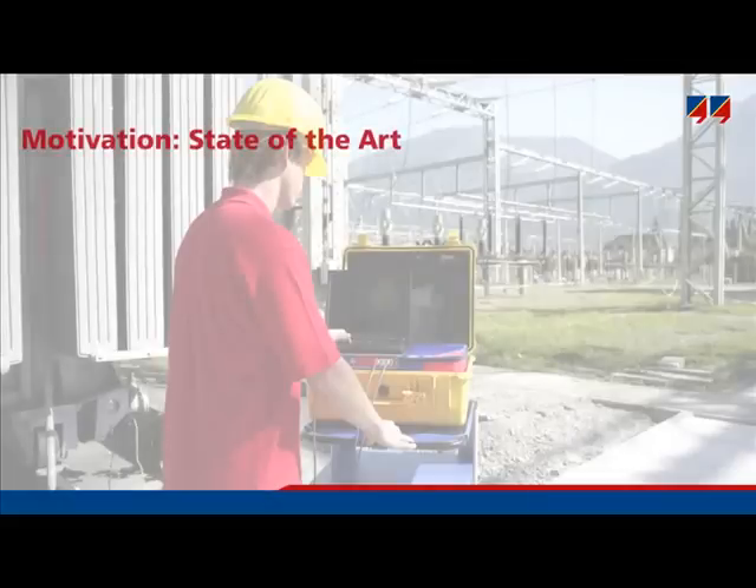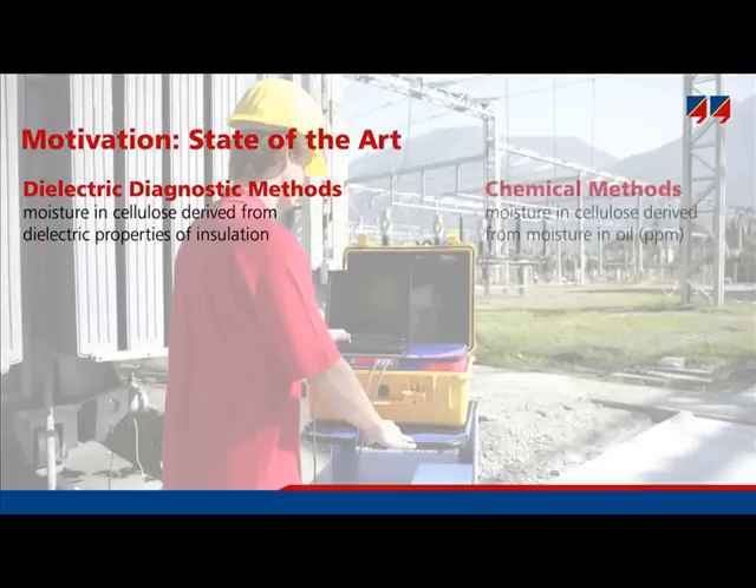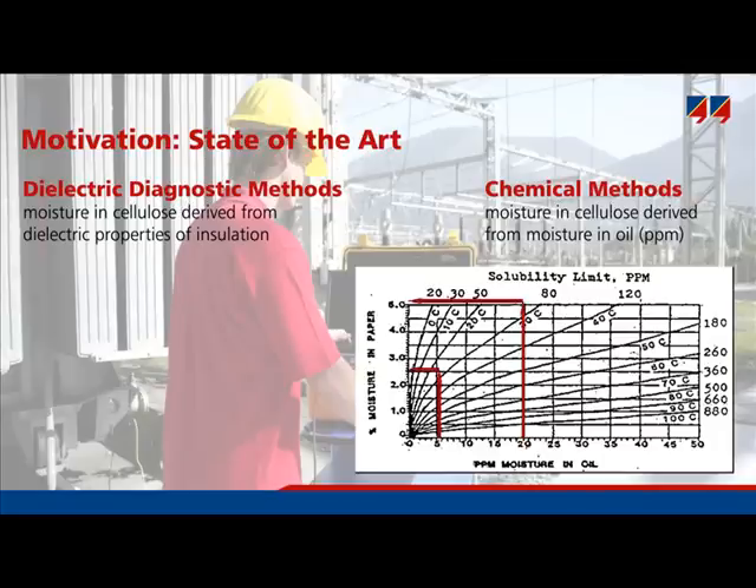To discover how wet a transformer is, there are at least two basic approaches. One is the dielectric response method, or dielectric diagnostic method — DIRANA belongs to this group. This method derives moisture content of solid insulation from dielectric properties such as dissipation factor or polarization currents. There are also chemical methods where moisture content in oil is measured, an equilibrium diagram is explored, and moisture content in paper is derived from moisture in oil. This conventional approach has been used for 20 to 30 years.